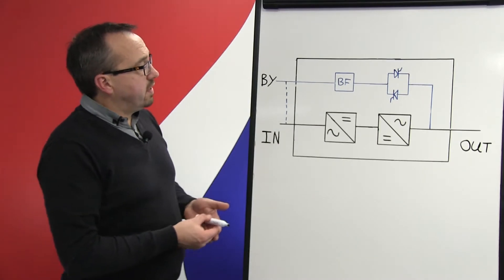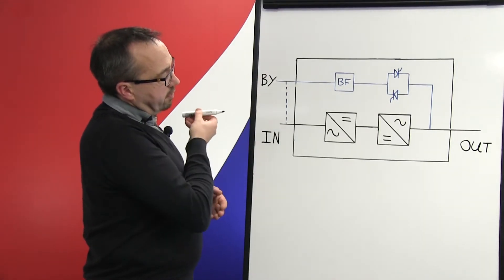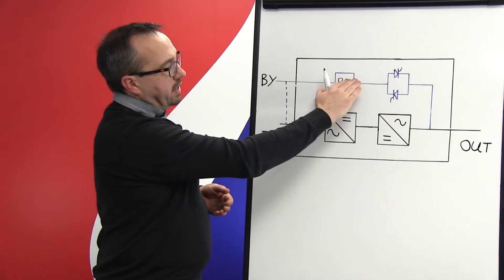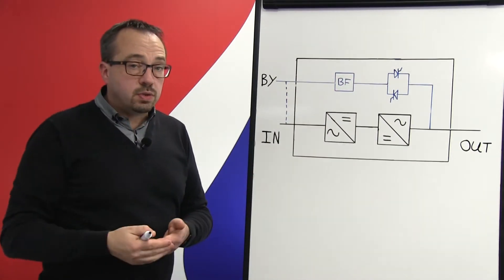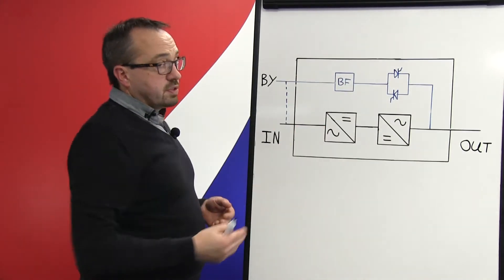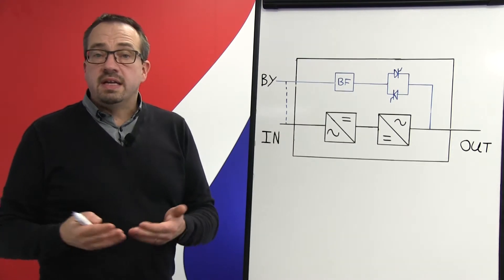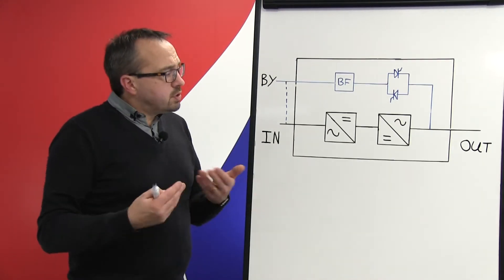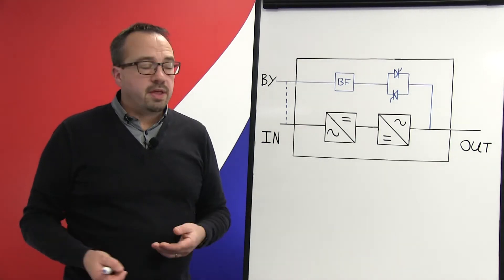Then effectively there are two supplies coming into the UPS system, and therefore the bypass supply here is on its own dedicated source and the rectifier is also on its own dedicated source, hence the term dual input. In terms of resilience, the dual input option is the preferred method.